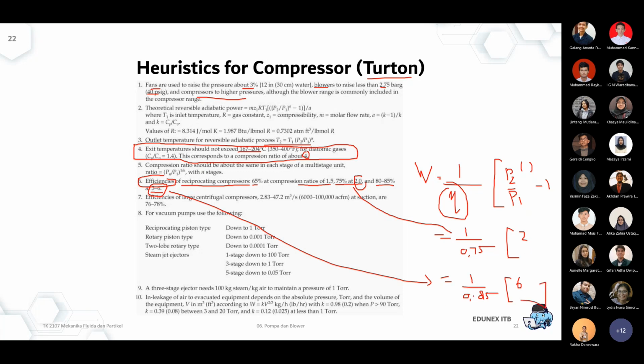The total overall duty could still be higher even though you have a higher efficiency. Okay? Why? Because you have a pressure ratio. When you have a higher pressure ratio, you will have a higher temperature and higher compressor duty. Okay, so it's not too straightforward. So later we have to consider everything when we want to select the final decision of the compressor.